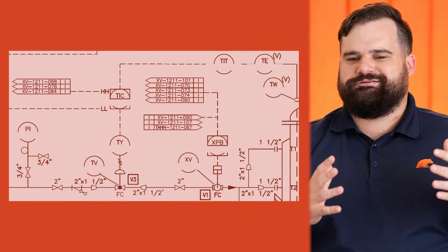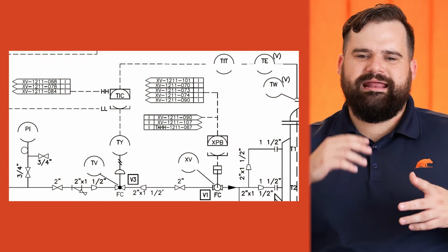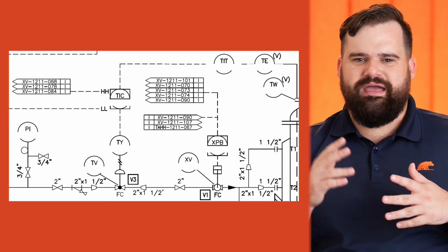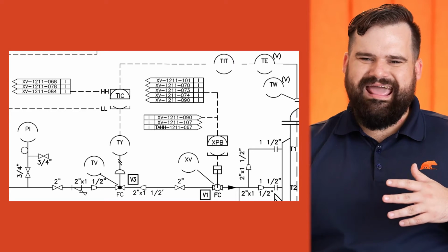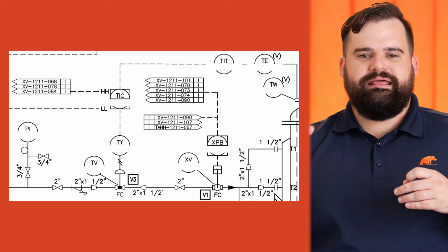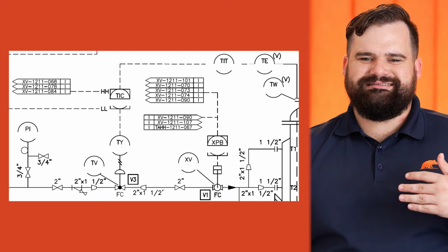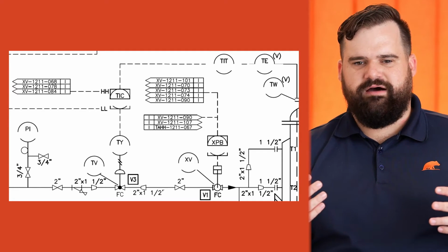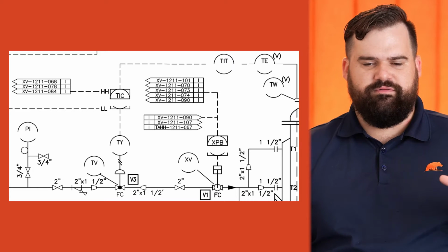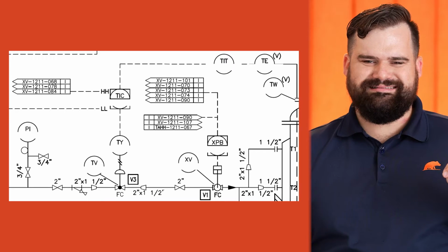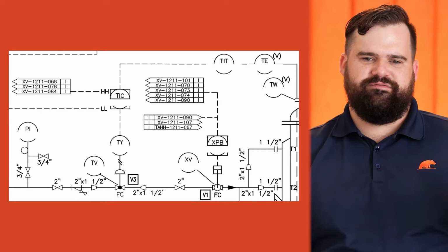Number one, we're talking about independence. As you can see on the screen coming up next to me, we're looking at a temperature loop and a temperature valve, right? So that valve may have an alarm, may have a switch on it. Next to it, you can see the XV in the same line, right? So we want that independence from the initial failure, and we want a separate interlock trip to trip that XV as a separate valve, right? And that's a true conservative level of independence, all right? That is tripping the system, and it's not tied to the loop or the initiating event, right?